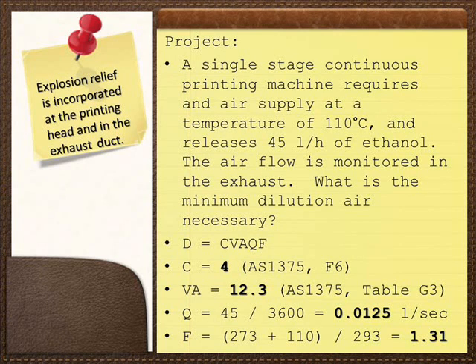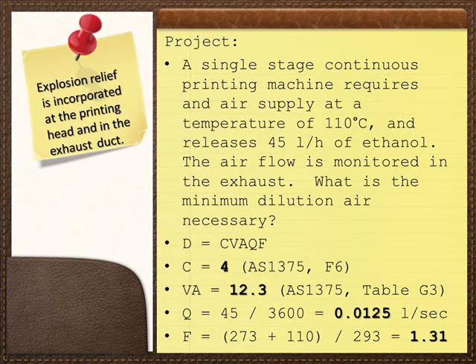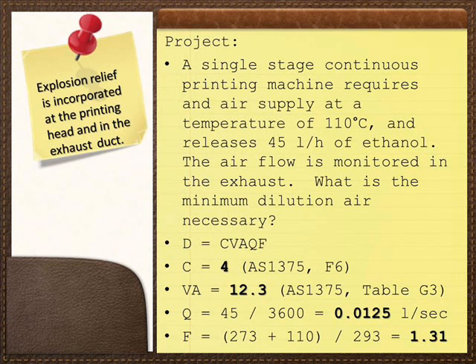What is the minimum dilution air necessary for this appliance? The equation is D equals C times V times A times Q times F. C equals 4, as per AS1375 Appendix F clause 6. VA is looked up in Table G, which gives 12.3. Q is 45 litres per hour and needs to be converted to litres per second. F, because the air temperature is 110 degrees C, needs to be calculated and equals 1.31.